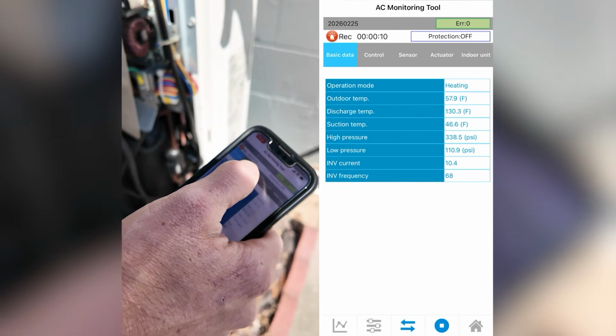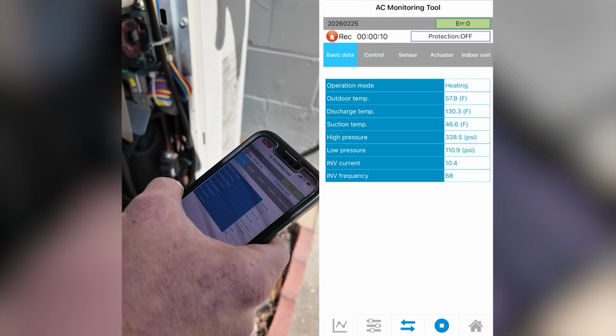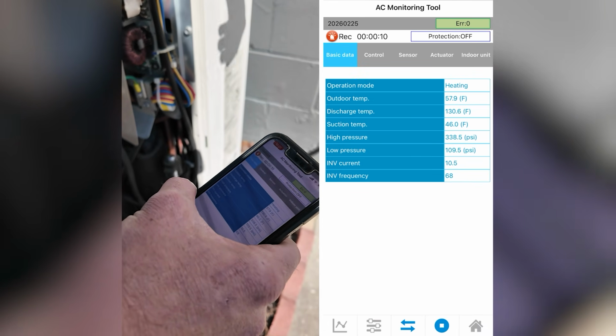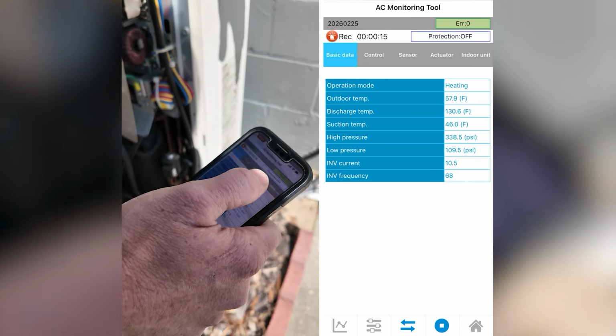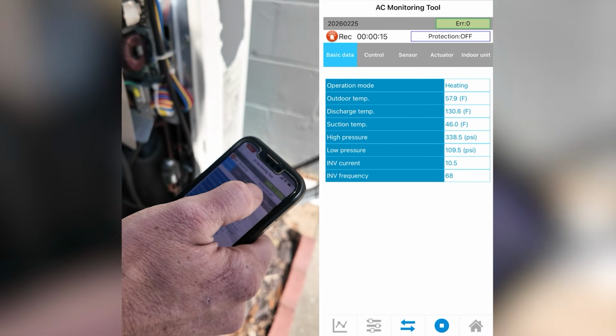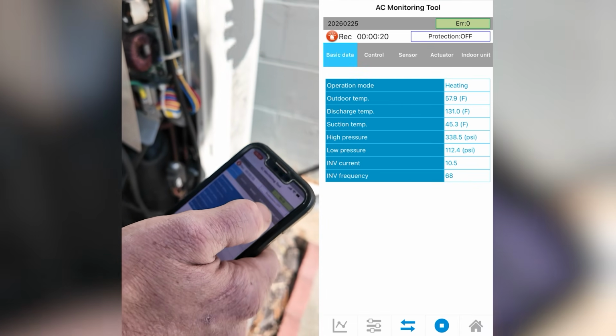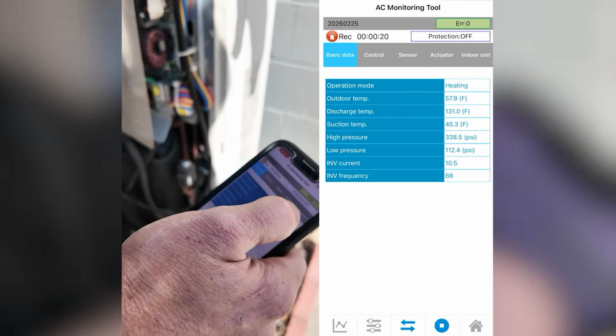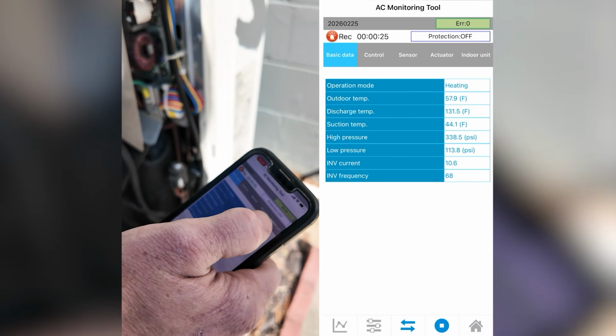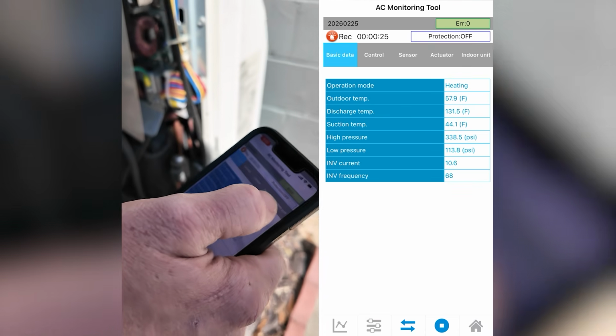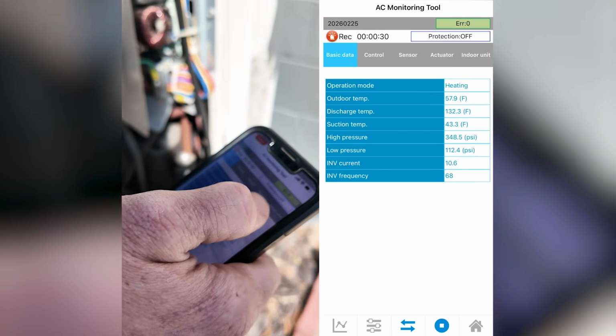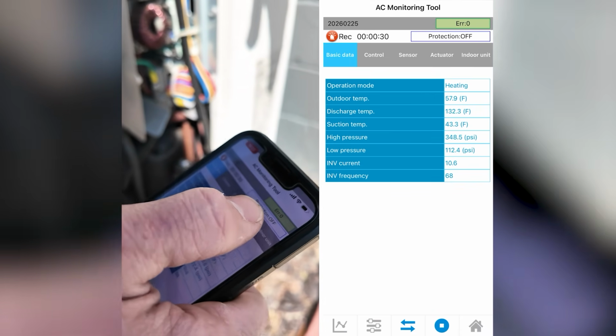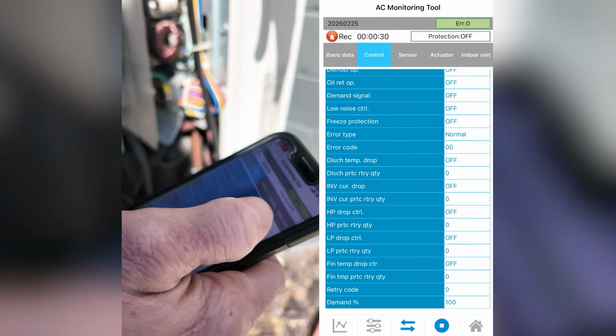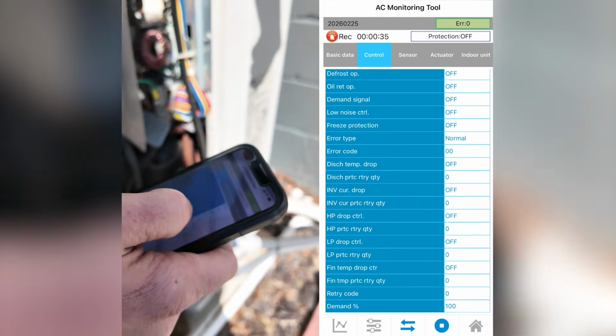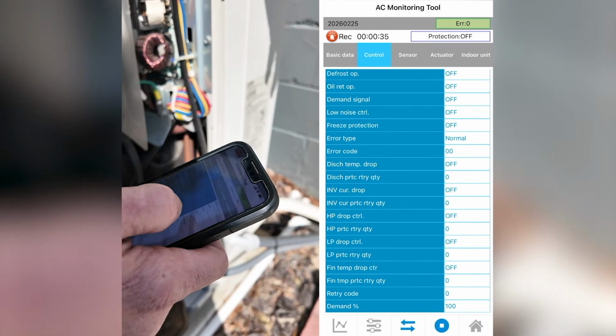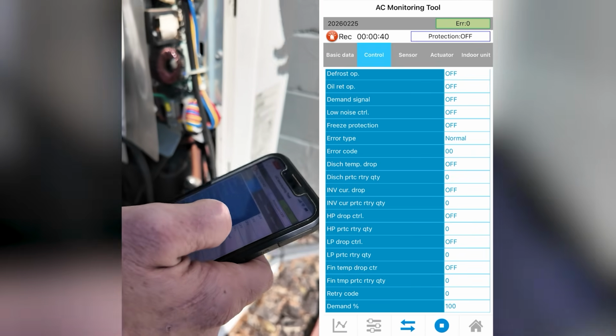If my mini split won't start and I've got flashing lights inside, but I can't find the error code, this type of service tool allows me to hook up to it to not only read the error code on the system, but also if there's any protection devices that maybe are keeping the compressor from ramping up. Maybe you've got a system where the system isn't delivering the design capacity, but you don't know why it won't ramp up. And it's not because it's undercharged or overcharged, it's because there's probably a protection control on the control screen that is active, keeping it off. You find the one that's on, you go to the service manual and you find out what the conditions are and why it's off, and then troubleshoot from there.